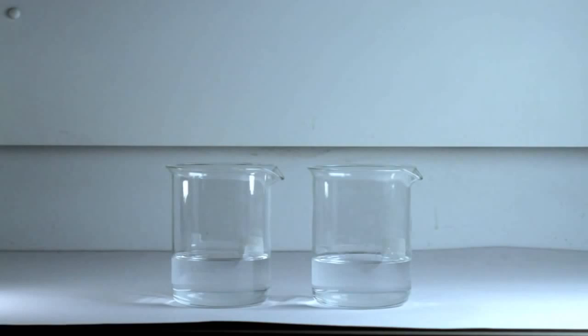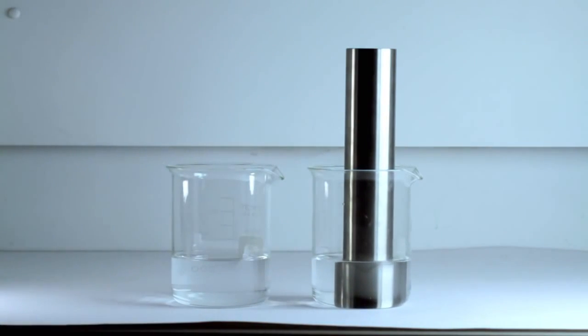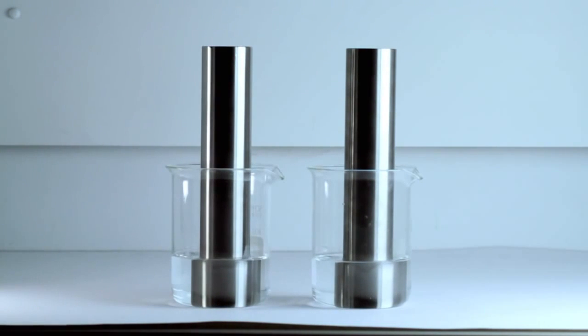And before they leave us, they're thoroughly polished and cleaned to ensure the most hygienic surfaces possible and the lowest risk of contamination. But don't take our word for it. Take a look at this. We are dipping these tubes in phosphoric acid to see how clean they really are. As they react with the acid, the presence of contaminants such as polishing compounds shows up as discoloration. These are extracted by the acid, just like in a typical cleaning cycle.